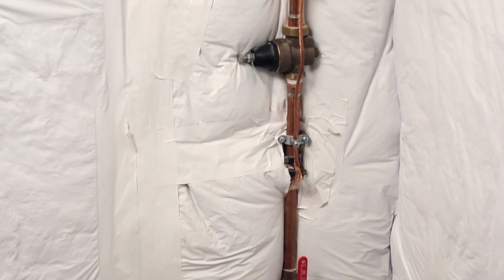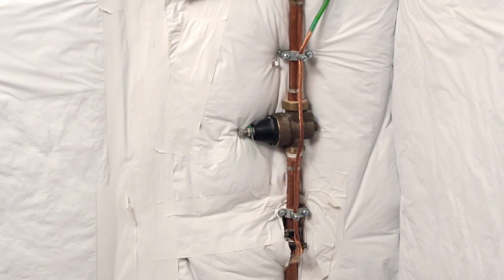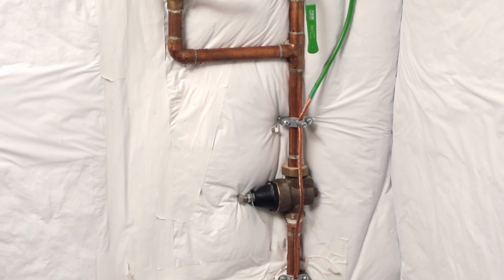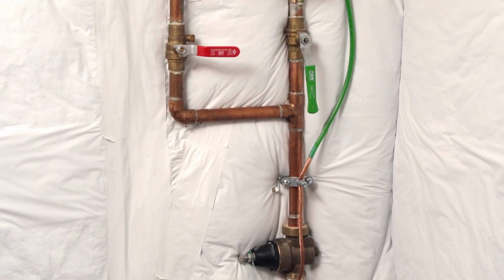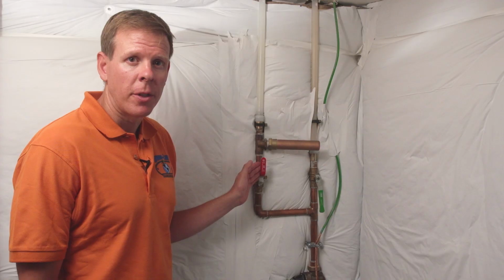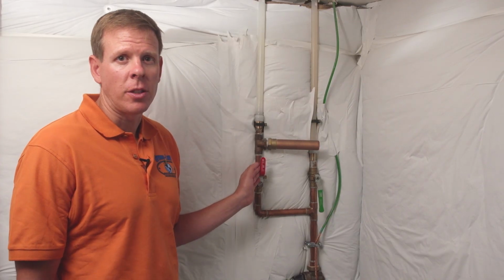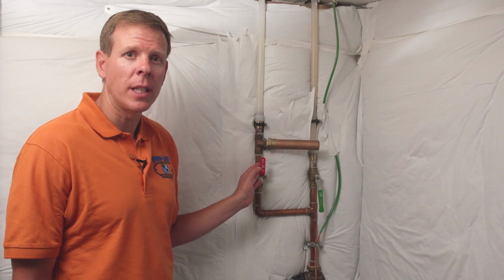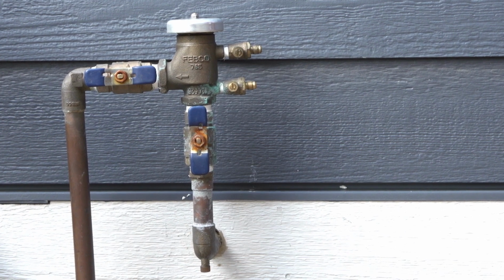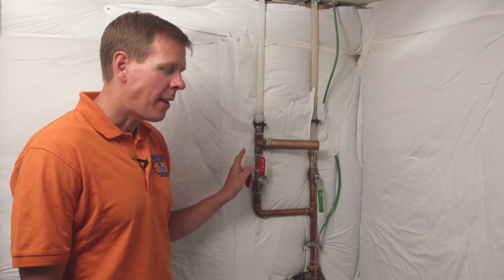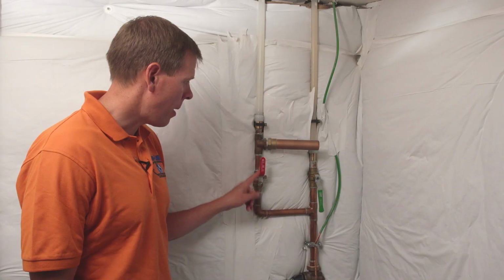The first thing we need to do to drain the basement pipe is find where the water shutoff is to the sprinkler system. It is typically in the basement or the crawl space. But if you're not sure, the best way to figure out where the shutoff is, first find the backflow preventer or vacuum breaker and trace the pipes backwards. Then it is typically either a gate valve or, in this case, a ball valve.